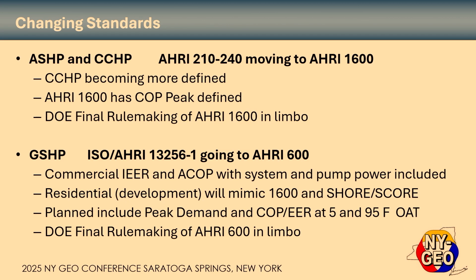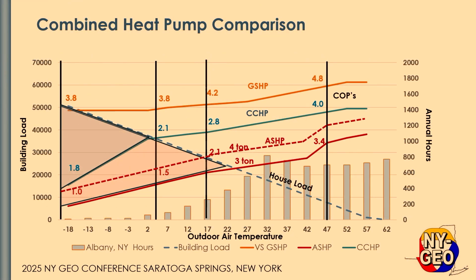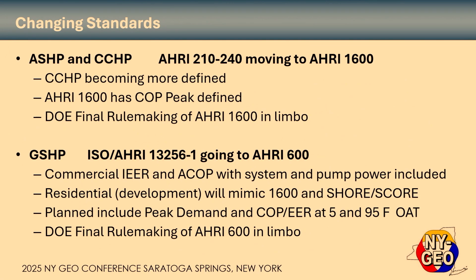AHRI 1600 has a COP peak defined, and so that's a system peak. So if we go back to this slide here, it actually defines that in heating and cooling. And so at 5 degrees, it's defining that peak as the whole system. And so if you sized here, it would really just be the equipment itself. But if you actually picked this temperature down here, you would have to add in the COP of the electric heat in there as well. So it really depends on where that's done at. But at least there's an effort there to try and put some sort of a peak COP in both heating and cooling into the standard.